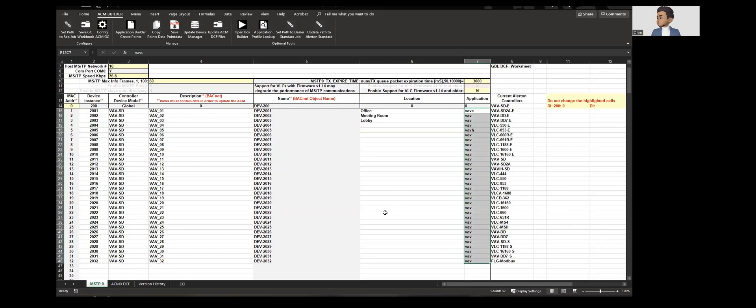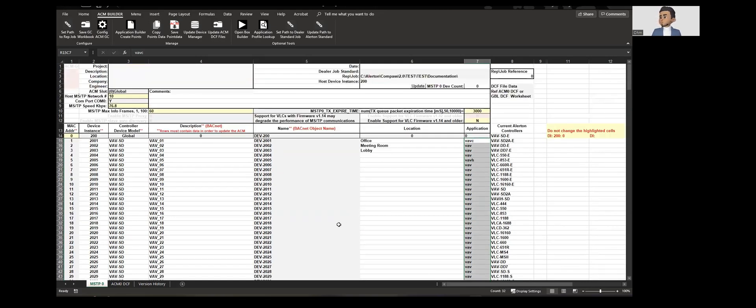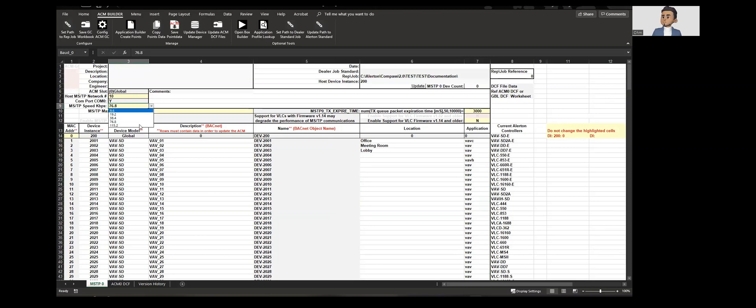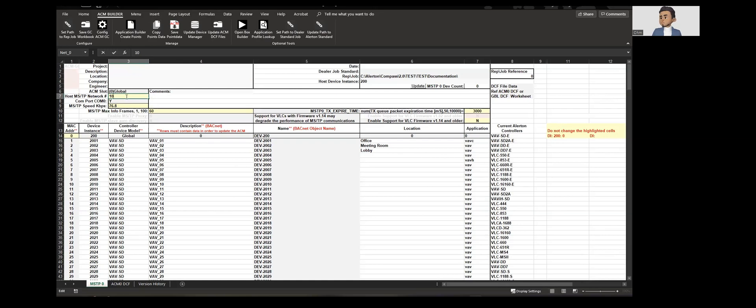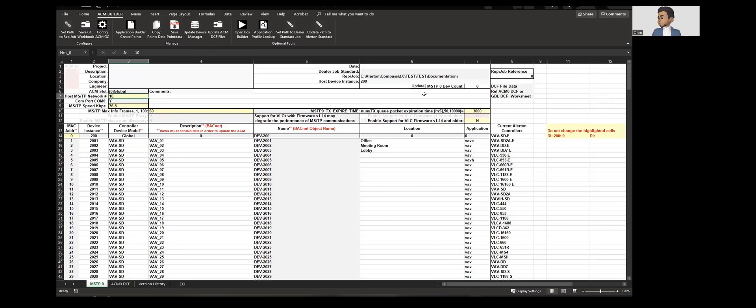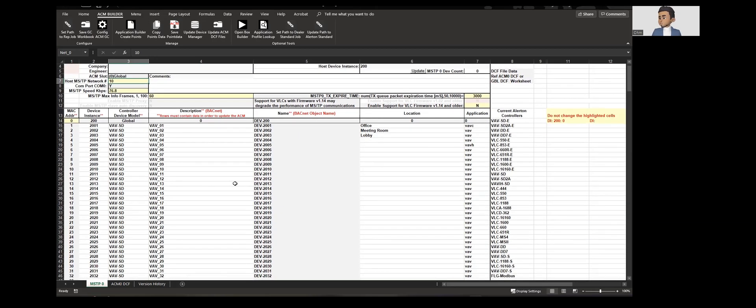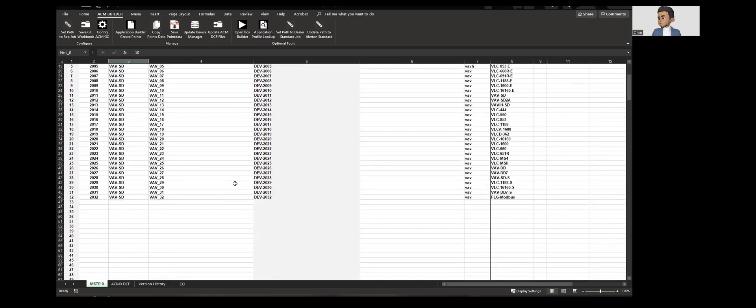Once this is created, there are a few other settings. Let's say if the MSTP loop is set up for 76,800, you could choose that. Then make sure your host MSTP network number is matching. Currently if you are using 101 I believe in the previous one, but again just make sure you have to update this. That's all what you have to do here.